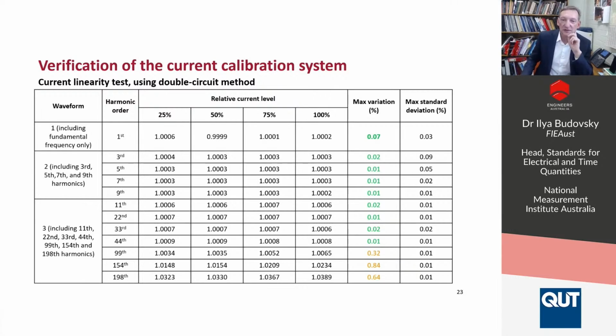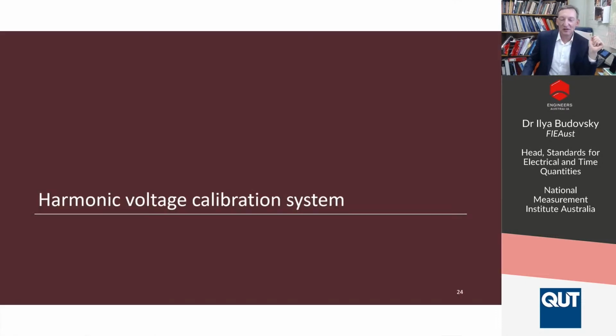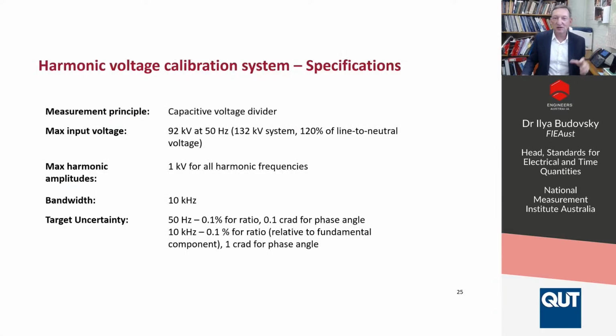So this is more or less all about the current system. Let us now go to the high voltage system. Here again, we need to generate 50 hertz, in this case 92 kilovolts for a 132 kV system, and harmonics synchronized with the fundamental. Luckily for voltage, we only need 1 kilovolt in harmonics. And again, we are working with a bandwidth of 10 kilohertz, and our target uncertainty is 0.1%, even though we want to do much better.